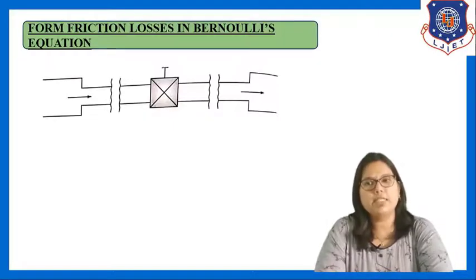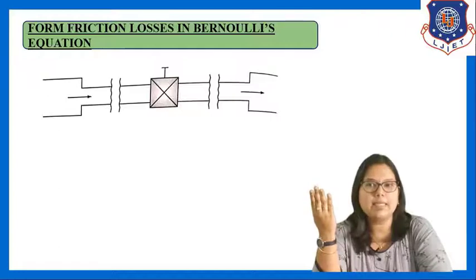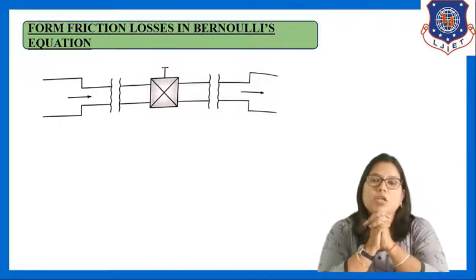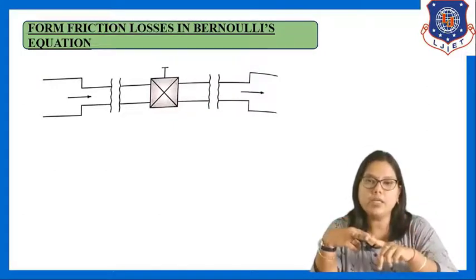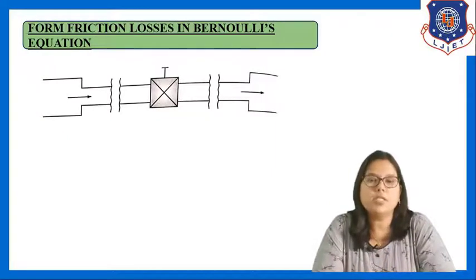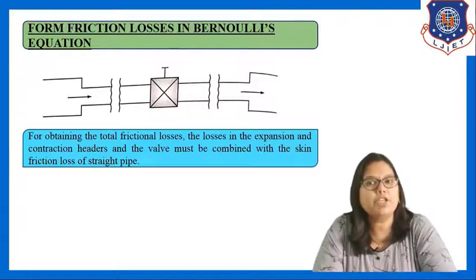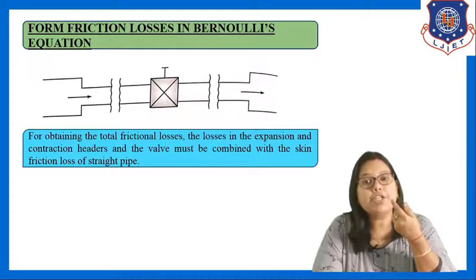Now let us look at form friction losses in Bernoulli's equation. In the figure, one side has sudden contraction in area, the other side has sudden expansion, and in the middle part fittings are used. For obtaining total frictional losses, losses in the expansion, contraction, headers, and valves must be combined with skin friction loss from the straight pipe. Total friction loss includes skin friction as well as form friction due to sudden expansion, sudden contraction, and due to valves and fittings.